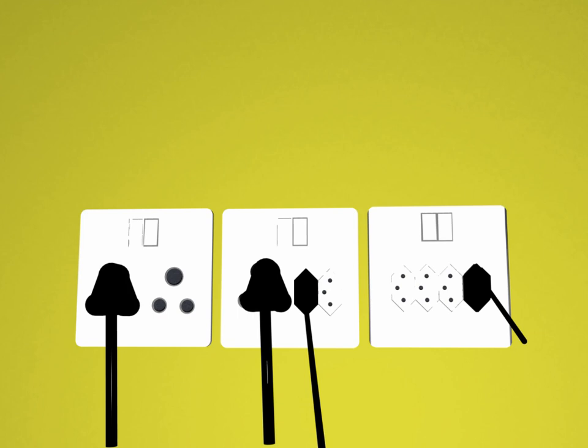Brazil uses both 127V and 220V mains supplies, but rather than using the IEC 60906-2 standard for the lower voltage it uses NBR 14136 for both. Whereas IEC 60906-1 specifies a single 16A rating with 4.5mm pins, NBR 14136 has both 10A and 20A ratings. The 10A plug has a pin diameter of 4mm, and the 20A plug is 4.8mm. NBR 14136 does not require shutters on the apertures, a further source of non-compliance with IEC 60906-1.